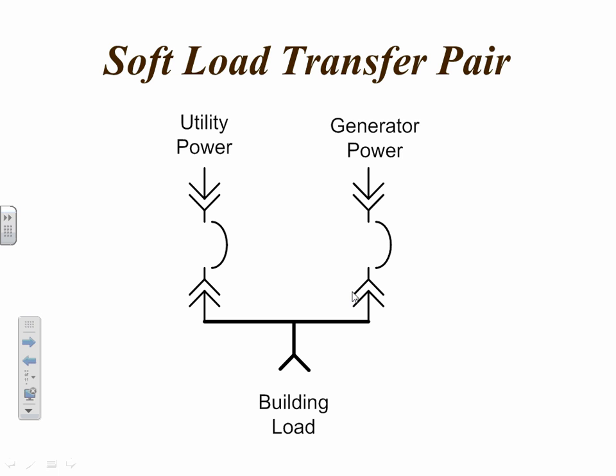Here's what it looks like, and here's what happens. It's got utility power coming in here, going through a utility main, and this is all in one box, by the way. Three sets of contacts. Utility power comes in, supplying power to this bus that the building load is connected to, so it goes right into the building. Okay, now we've got our generator sitting out there near the transformer.